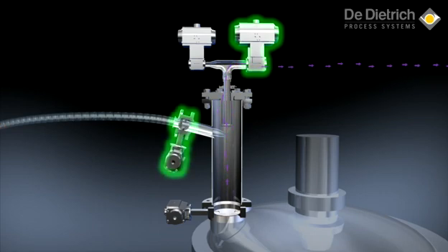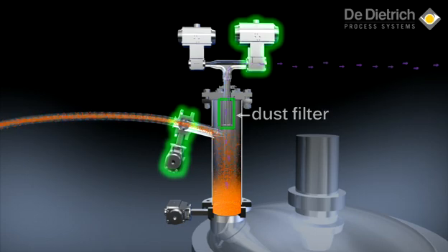After a predetermined time, the powder inlet valve opens and solids are drawn into the body. Entrained gas is evacuated through the internal dust filter element, and the solids are retained inside the body.